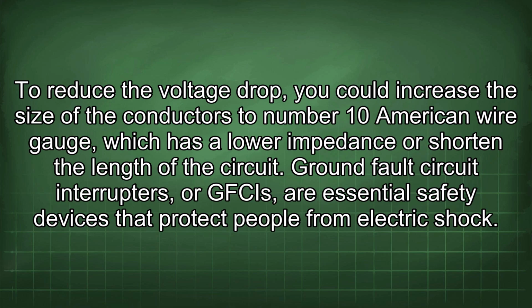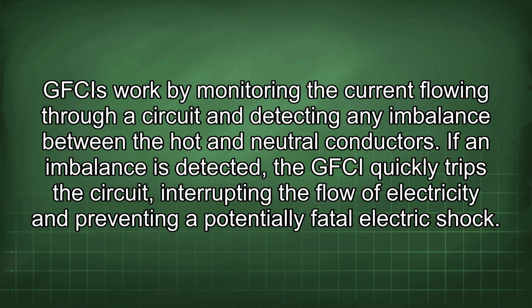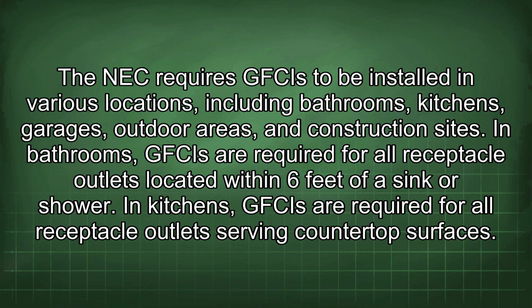Ground fault circuit interrupters, or GFCIs, are essential safety devices that protect people from electric shock. GFCIs work by monitoring the current flowing through a circuit and detecting any imbalance between the hot and neutral conductors. If an imbalance is detected, the GFCI quickly trips the circuit, interrupting the flow of electricity and preventing a potentially fatal electric shock. The NEC requires GFCIs to be installed in various locations, including bathrooms, kitchens, garages, outdoor areas, and construction sites. In bathrooms, GFCIs are required for all receptacle outlets located within 6 feet of a sink or shower. In kitchens, GFCIs are required for all receptacle outlets serving countertop surfaces.